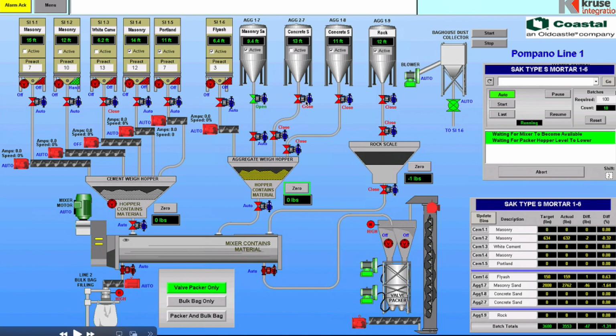If you have a valve in the closed mode, the PLC will not call that to come on. Well, that's not necessary for these. You may have these closed because these ingredients aren't being used. So that's operator selectable, but you want everything in the auto mode. Like this valve here is auto. This is the valve that we pulse and open, in the code to put weight in from this silo here.